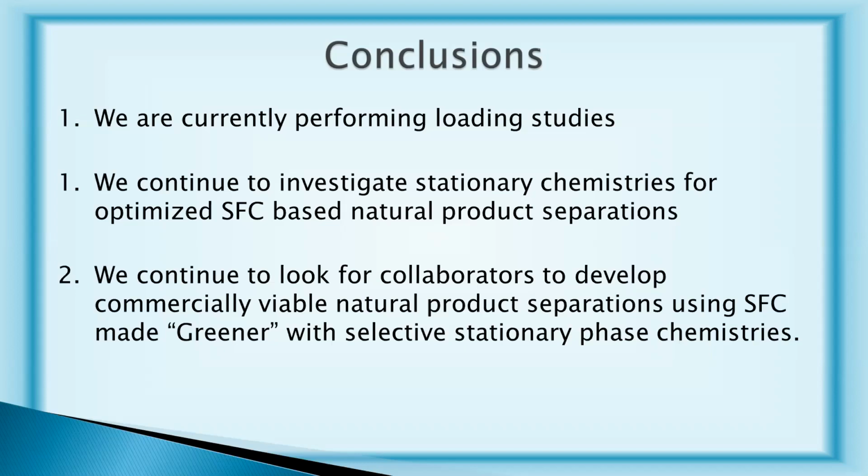Yes, I think in a lot of ways SFC is actually easier to scale than reverse phase chromatography. Going from the analytical size and scaling up to preparative size is pretty straightforward. SFC has the advantage that the back pressure is so much less that we routinely see columns that are 50 millimeter ID, a 2-inch internal diameter, packed with 5 micron packing.